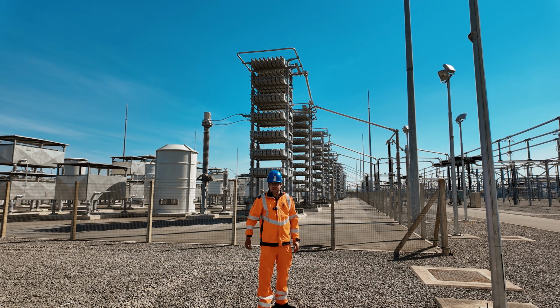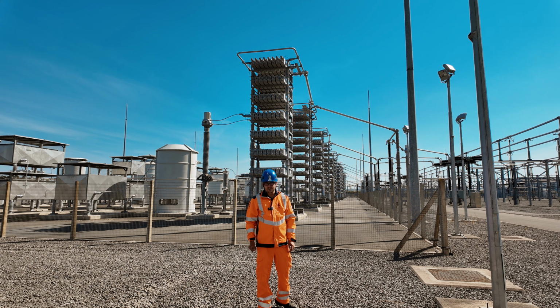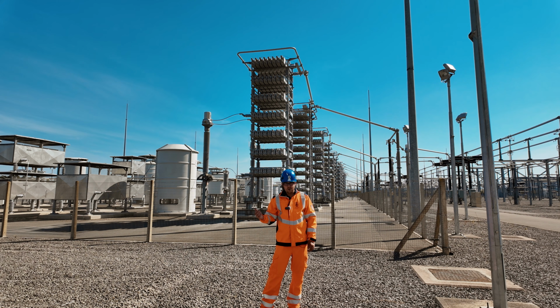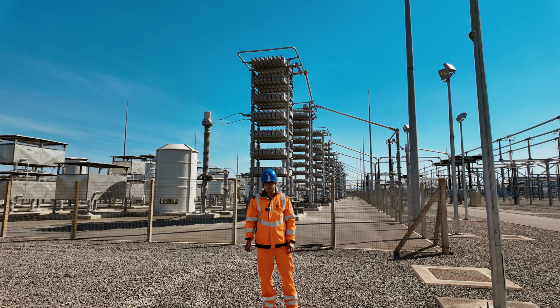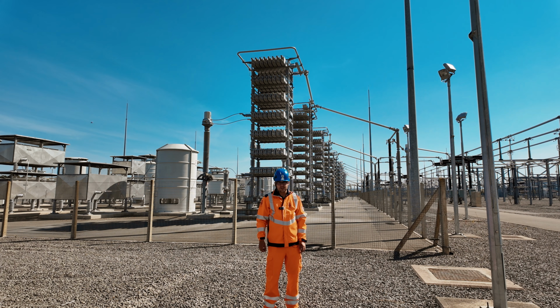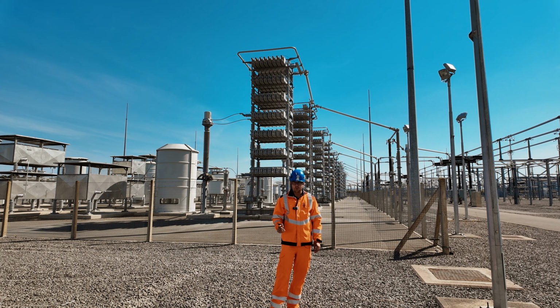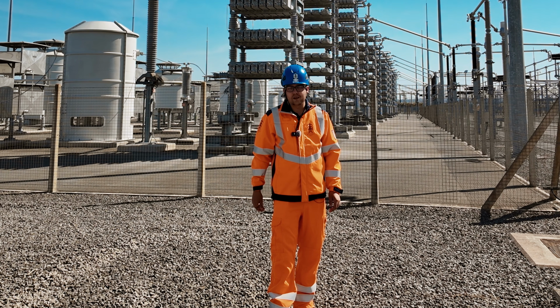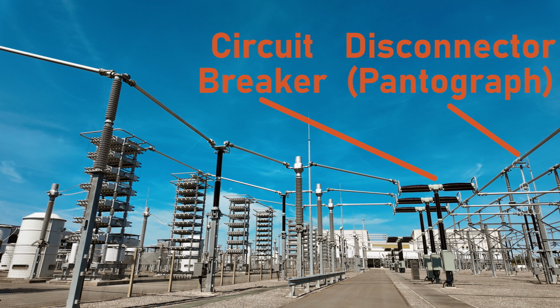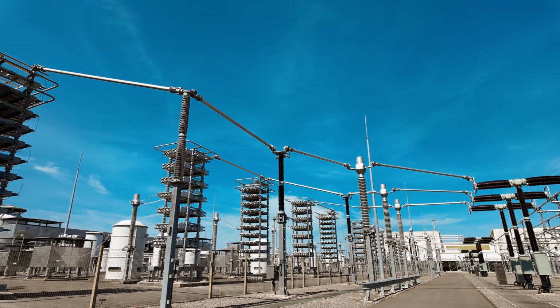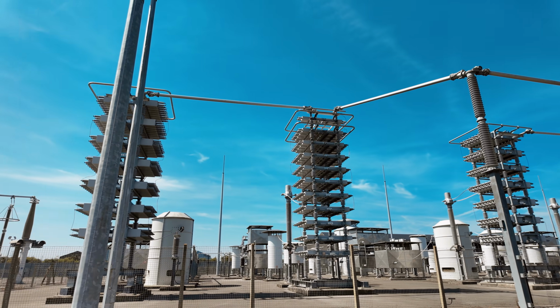And we've already established there's more than one harmonic frequency, so we tune our filters to attack or absorb certain frequencies. Because these are large, static pieces of equipment, connected at 400,000 volts, we can't tune them on the fly, so we have a filter per frequency we want to target. These are passive filters, meaning once we close the circuit breaker at the end of the circuit and the disconnectors, so it's connected to the system, it'll just work, happily, with no control needed.